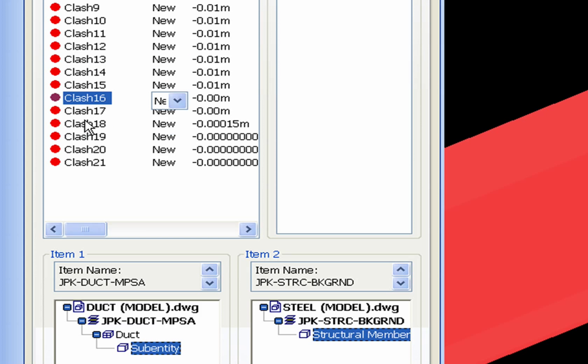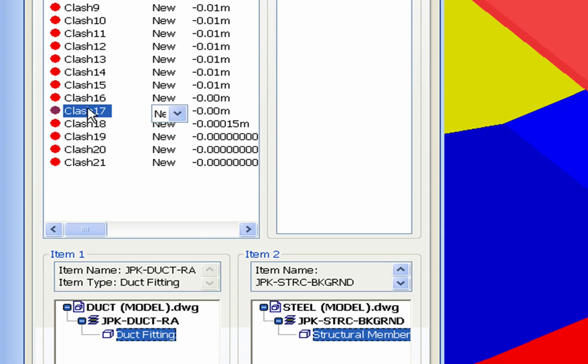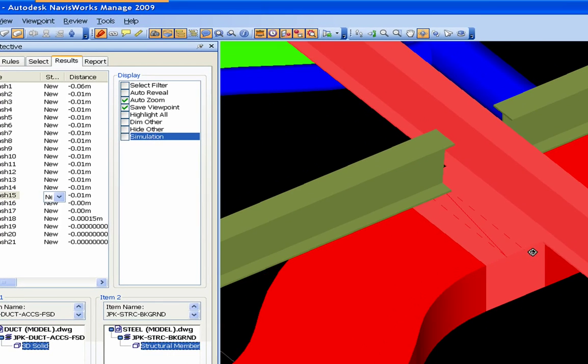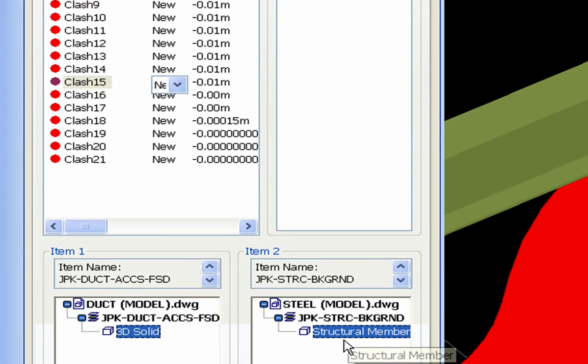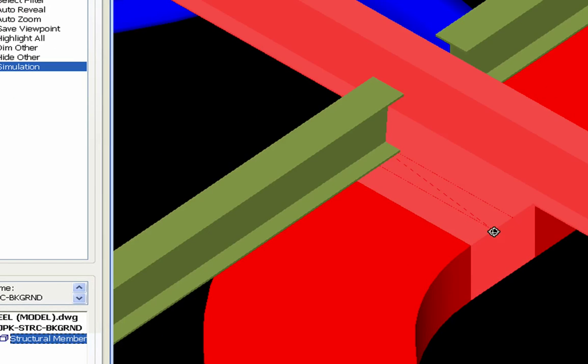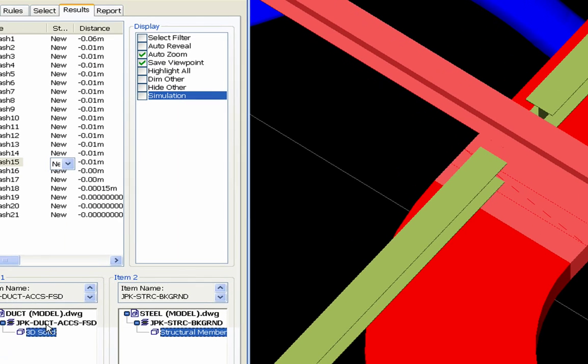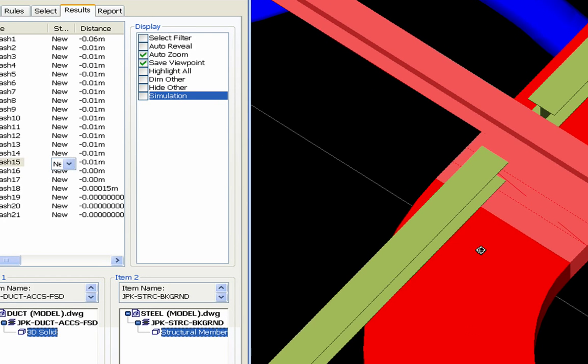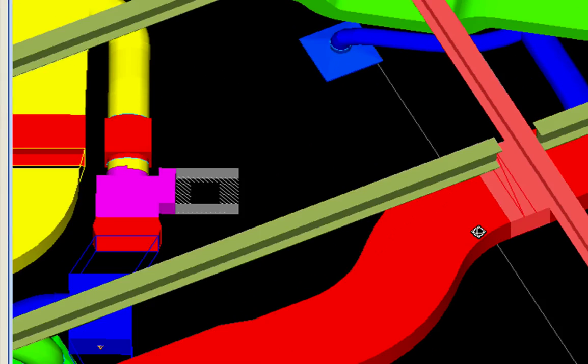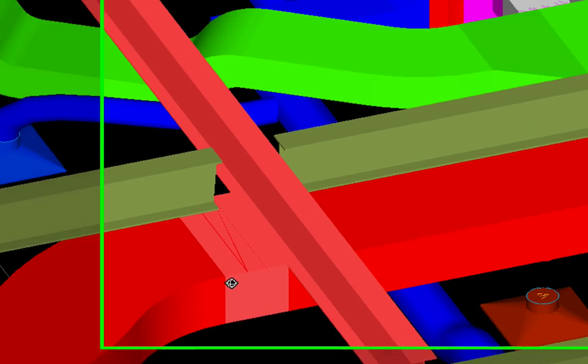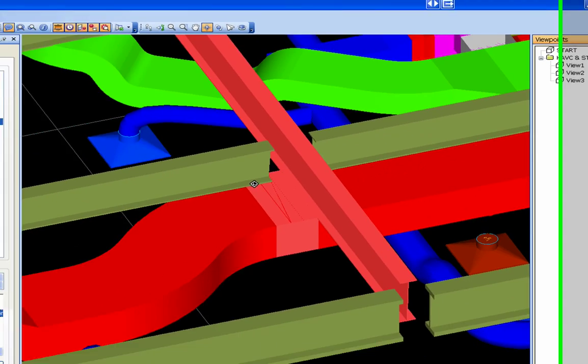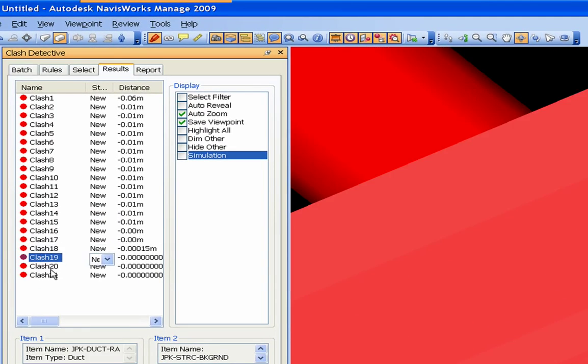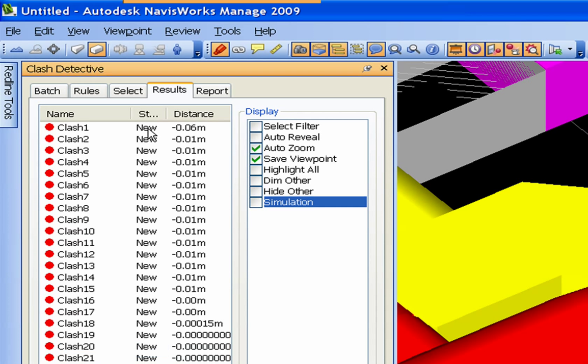And as you come down here, it tells you - this is kind of a window of what's clashing. You got a 3D solid, which is this steel, and a structural member. And the 3D solid is a fire damper and a structural member. As you can see, it's a duct accessory. And again, you can take a little snapshot of that or you can go into that.